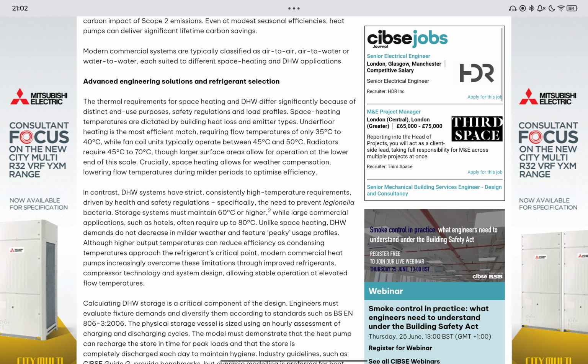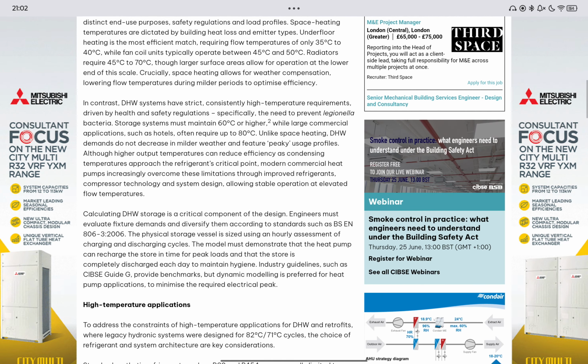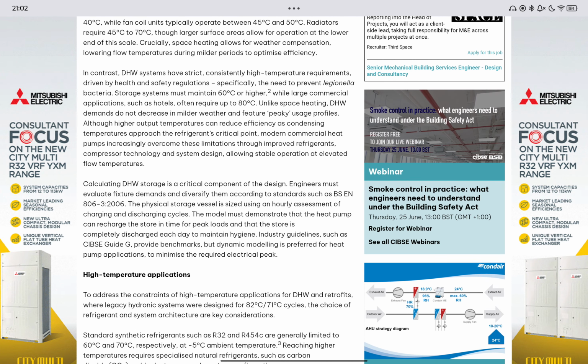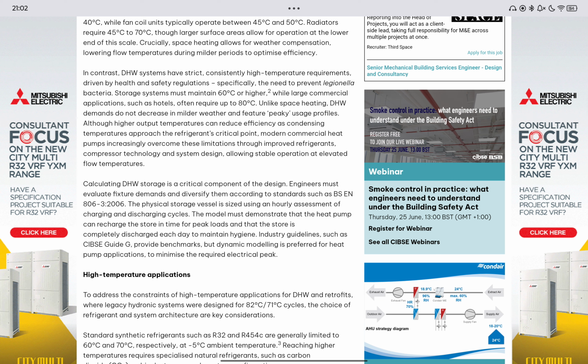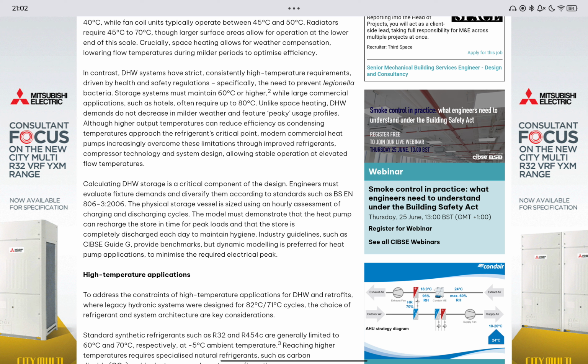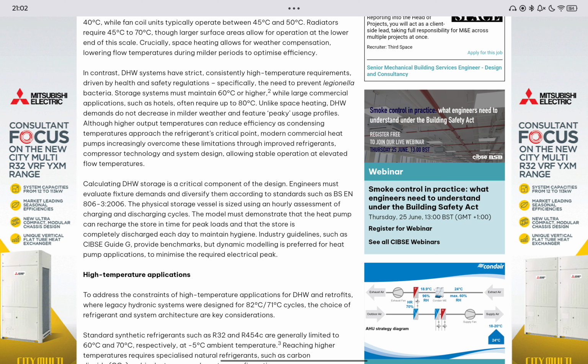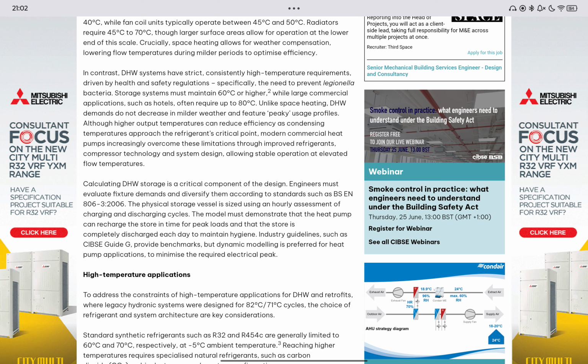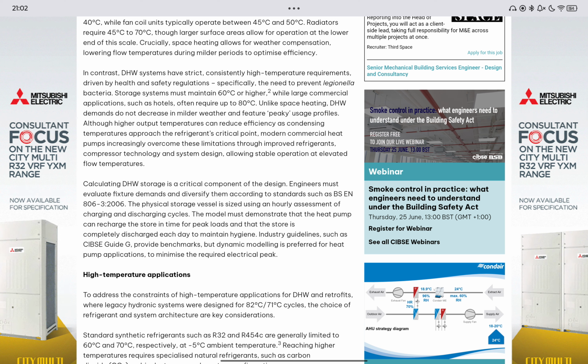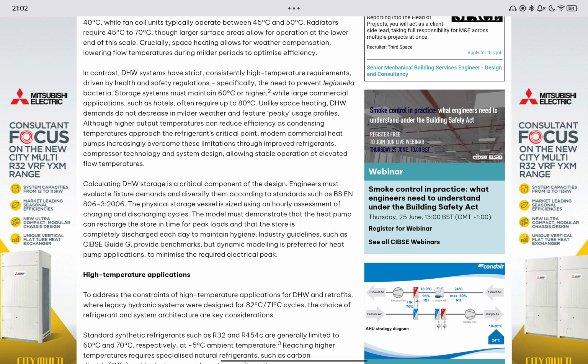Crucially, space heating allows for weather compensation, lowering flow temperatures during milder periods to optimize efficiency. In contrast, DHW systems have strict, consistently high temperature requirements driven by health and safety regulations, specifically the need to prevent Legionella bacteria. Storage systems must maintain 60 degrees C or higher, while large commercial applications such as hotels often require up to 80 degrees C. Unlike space heating, DHW demands do not decrease in mild weather and feature peaky usage profiles.